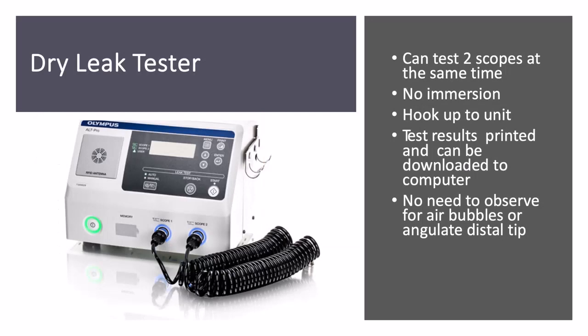There are new dry leak testers on the market that can test 2 scopes at the same time. You do not have to immerse them. You hook them up to the unit, and the test results can be printed and can be downloaded to a computer. There's no need to observe for air bubbles or angulate the distal tip. So manufacturers are coming out with better and more objective ways to test the scopes.